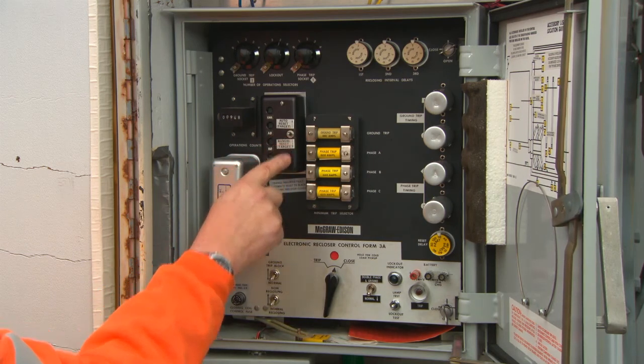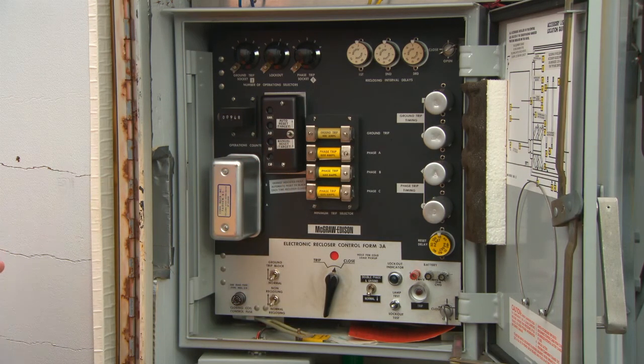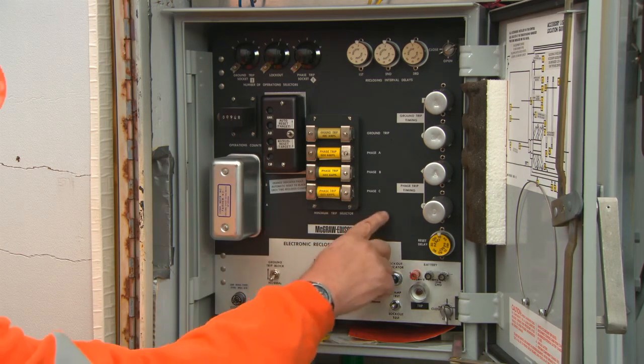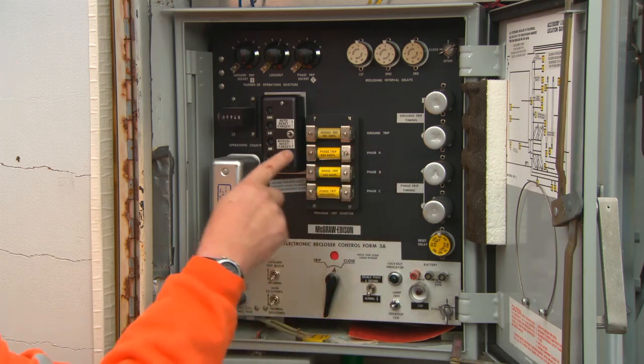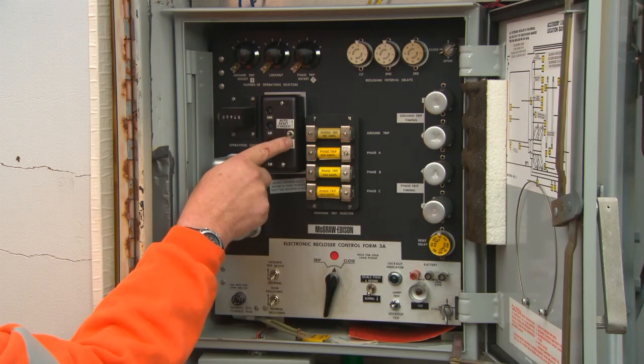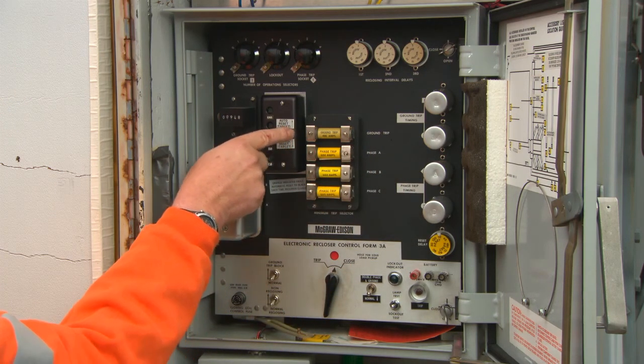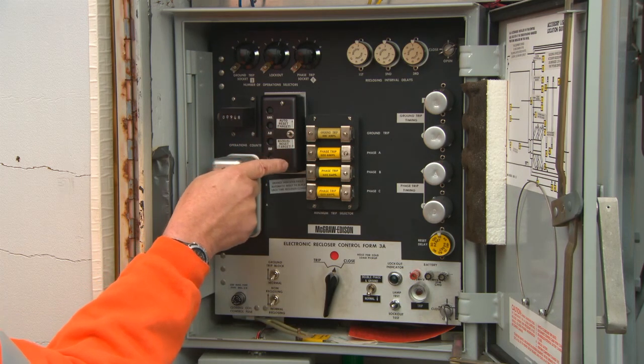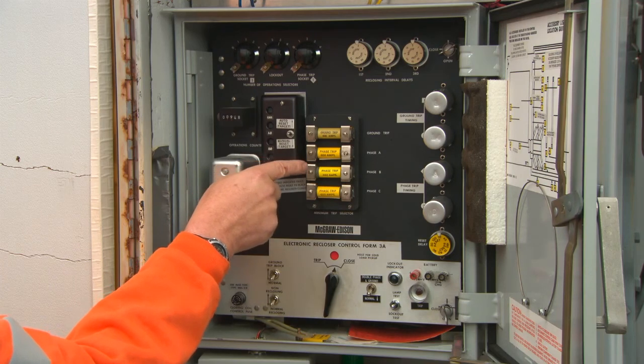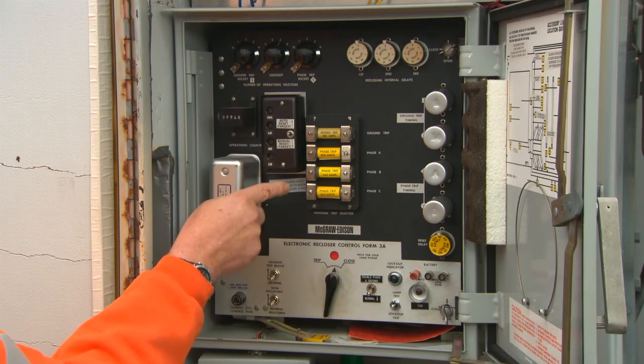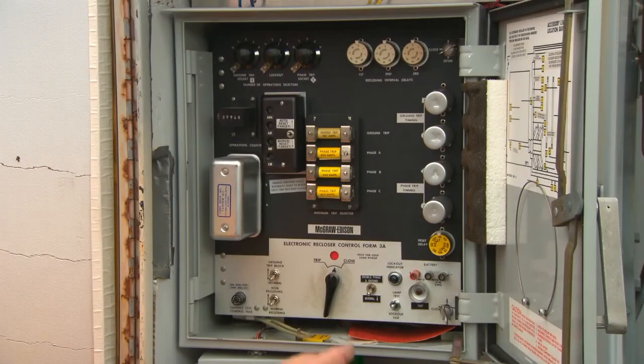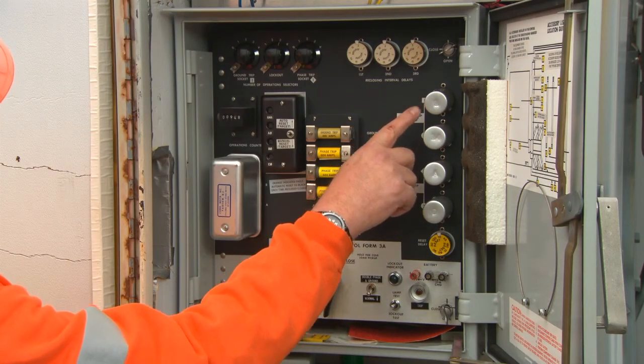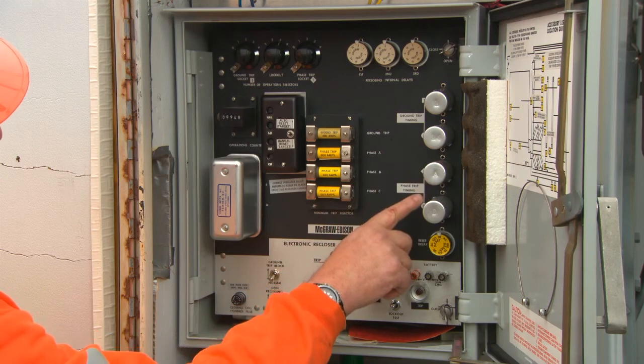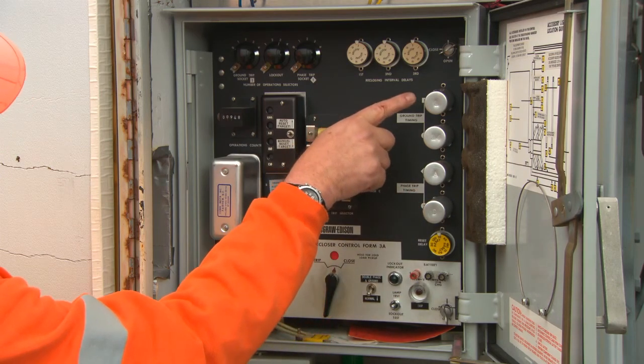Next are the 3 phases and ground trip yellow-colored resistors. Each one of these has a threshold trip value, in this case a 400 amp ground setting and 600 amp phase setting. The 600 amp trip settings for each phase are a gang-operated unit and cannot be operated individually. All 3 phases will trip when requested by the control. On the right side of the unit are silver-colored plugs, which provide a number of alternative timing curves for your ground and phase trip functions.